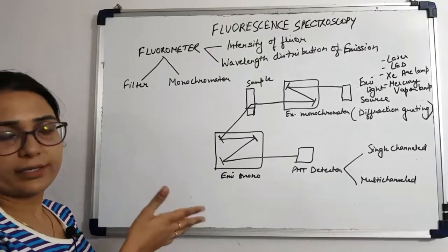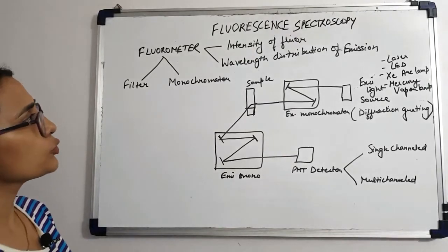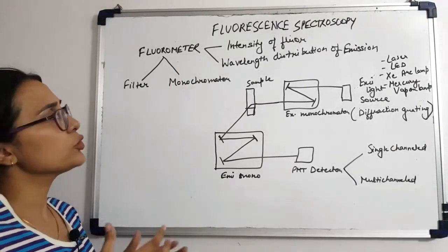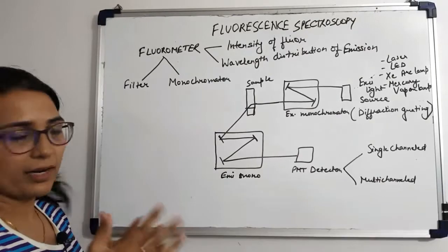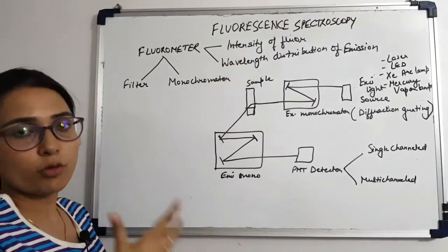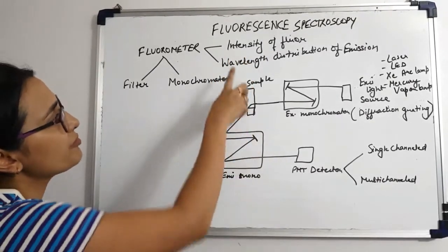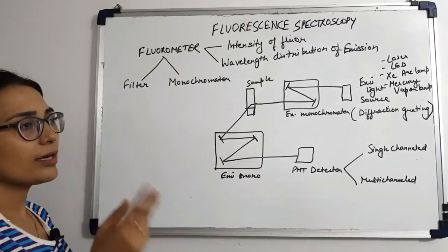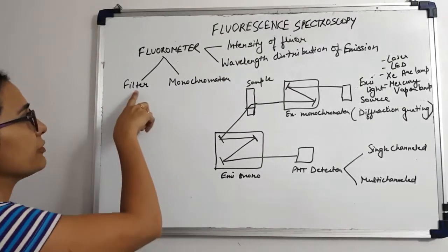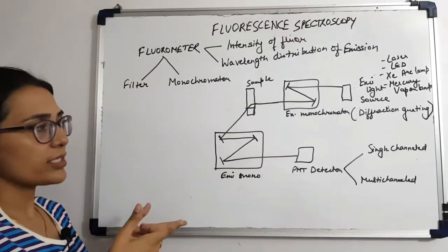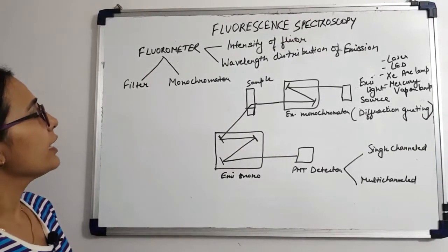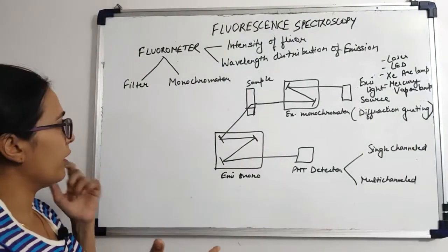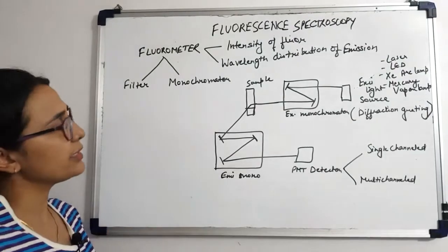Next, let's look at the instrumentation for fluorescence spectroscopy. The instrument used to measure fluorescence is known as a fluorometer. A fluorometer is used to measure different parameters of fluorescence, for example the intensity of fluorescence and the wavelength distribution of emission. There are two different types of fluorometer: one is a filter fluorometer, which uses a filter to isolate the incident light and the fluorescent light, and the other is a spectrofluorometer, which uses a monochromator to isolate the incident light and the fluorescent light.